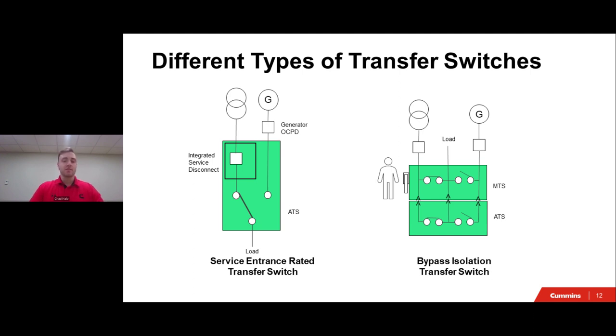Now, what defines a disconnect device is a circuit breaker that either forms part of your utility meter base or the main panel, which is also commonly referred to as the main breaker. This is great and this is awesome, but what exactly makes this a service-rated automatic transfer switch? That would be the ability for a transfer switch to have the breaker added in series with the utility input and a bonding jumper between the neutral and ground, all of which must be in accordance with UL 1008, which is one of those codes that I referenced and will be discussing a little later on in the presentation.